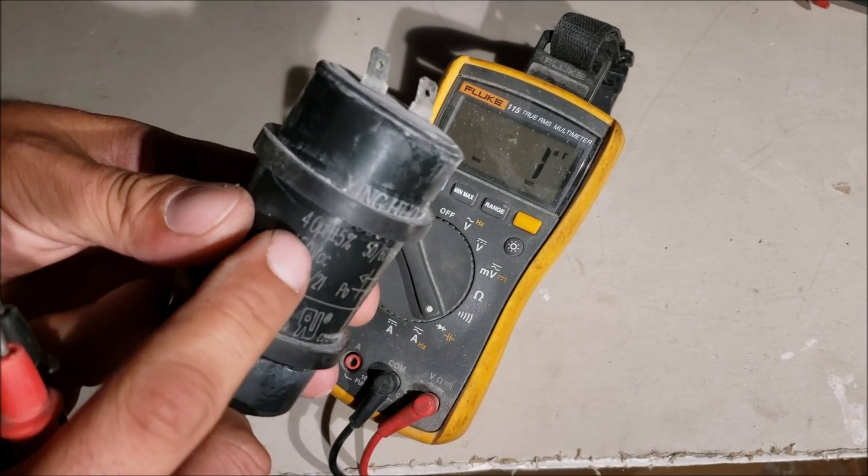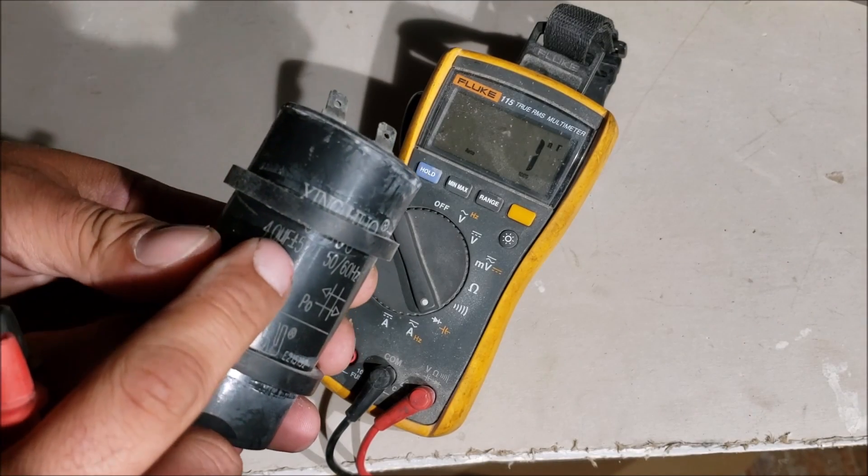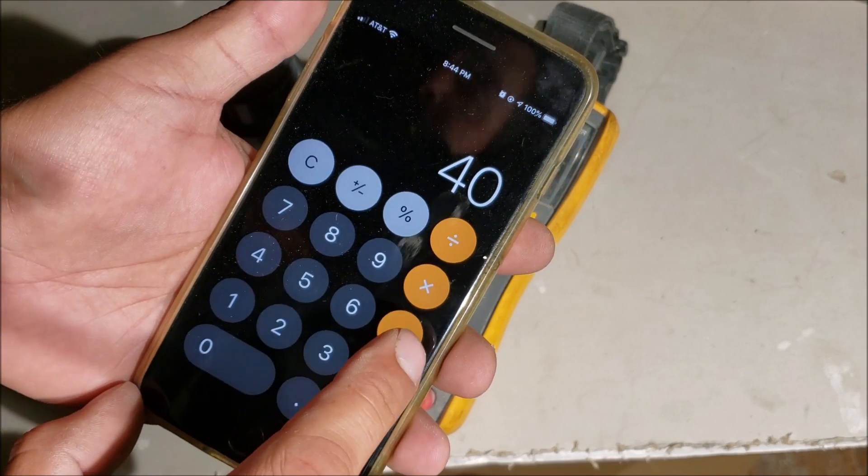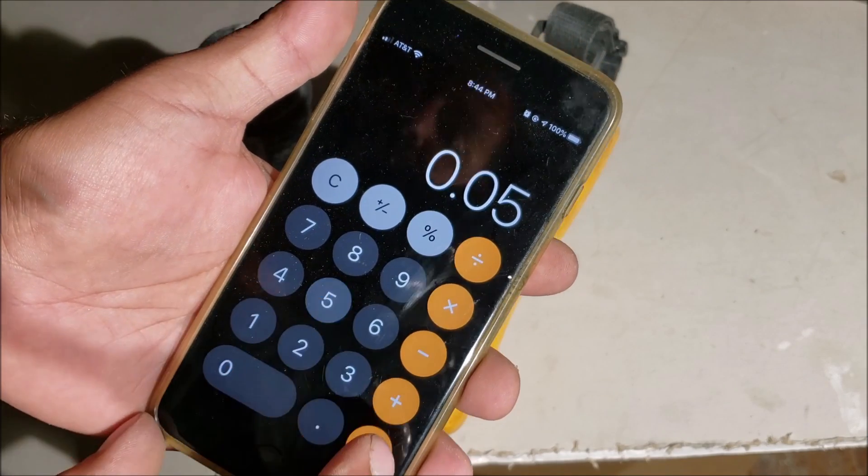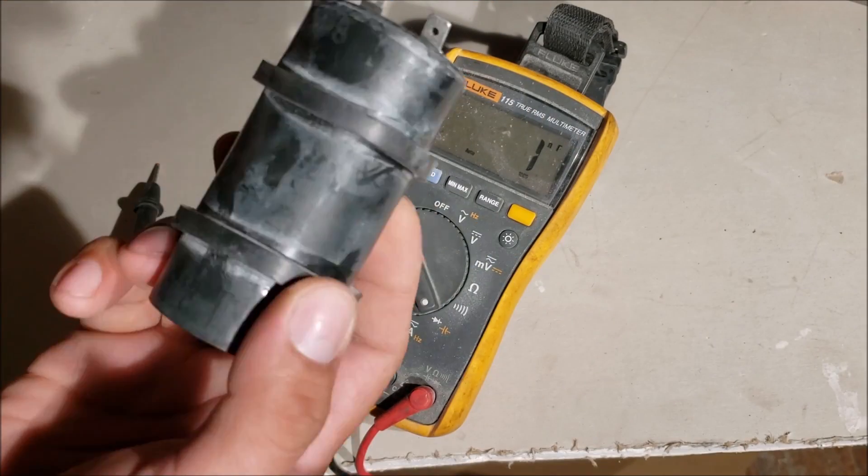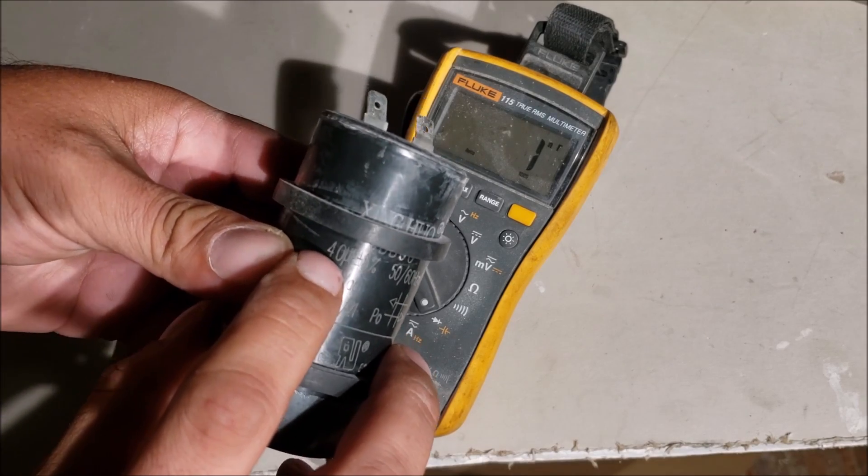Because this is the run capacitor off the same air compressor, it's showing a value of 40 microfarads plus or minus five percent. You take your 40 microfarads, multiply by a percentage of five, it gives you two. That means this capacitor must be in the range of minus two, which is 38, to plus two, which is 42 microfarads.